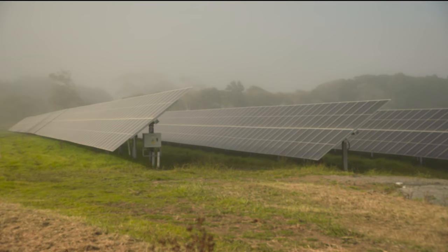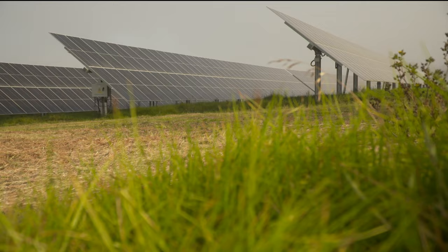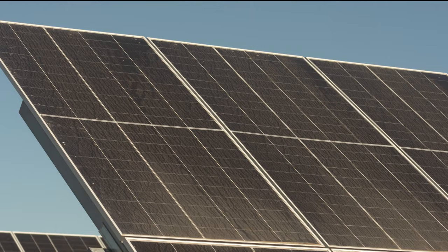It's Northland's famous hotspot that's finally been put to work. In field one there's approximately 10,000 solar panels — 540 watts each, about a metre wide by two metres high, with two of them in portrait. They've got about 300 kilometres of cable that takes power to each of the inverter boxes at the end, and then we invert that and connect it to the grid from there.